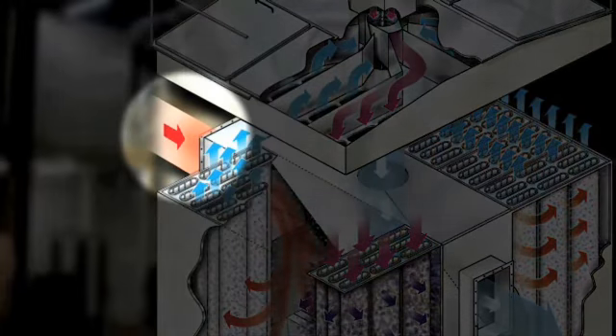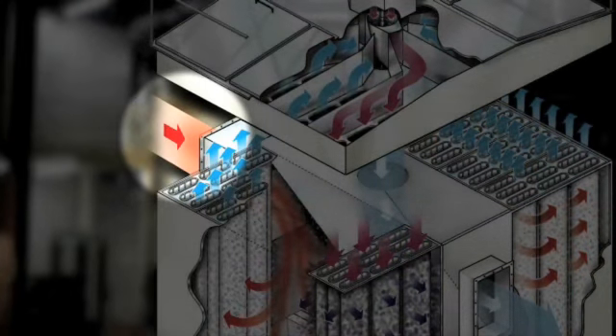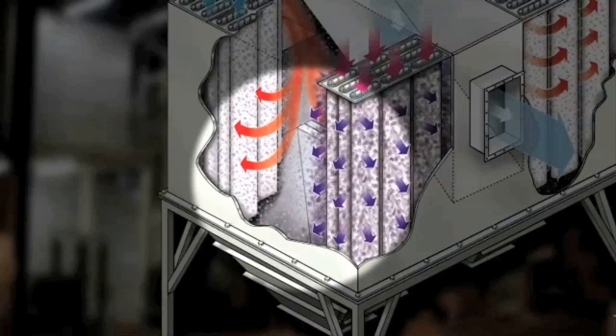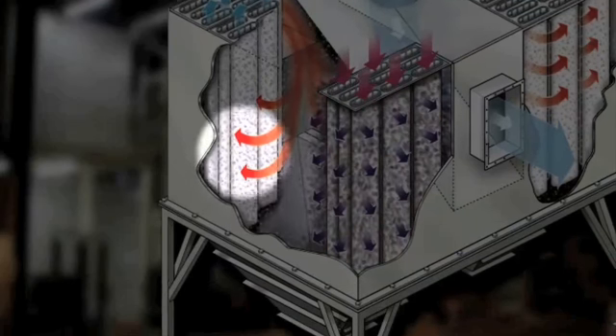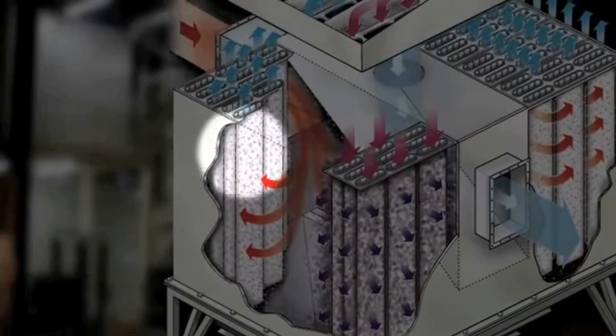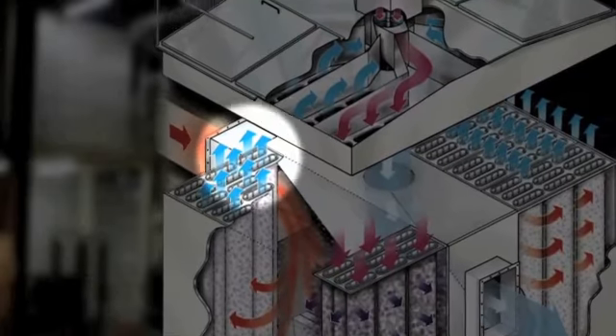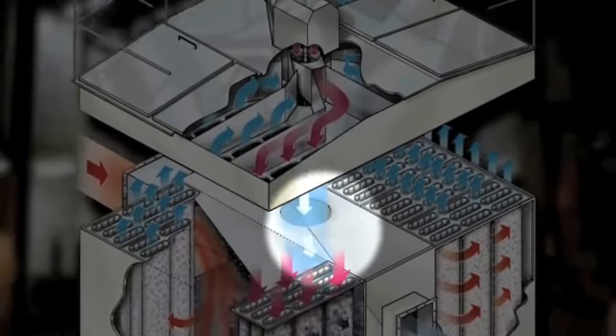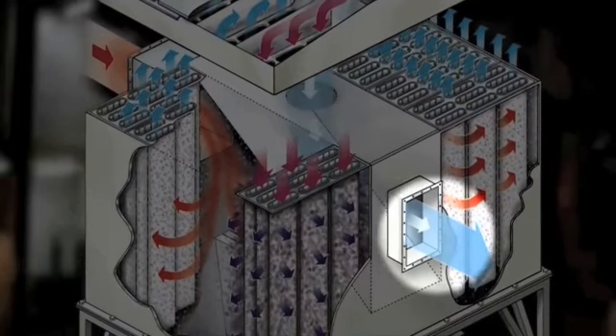Contaminated air is sucked into the filter by the main fan. As the air enters the filter center section and the speed is reduced, heavier particles fall to the bottom and into the dust hoppers — this is the first stage of cleaning. The air then passes through the numerous filter bags and up into the filter top, which is divided into separate compartments.